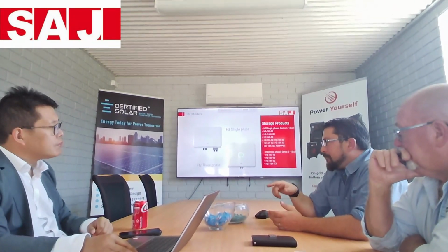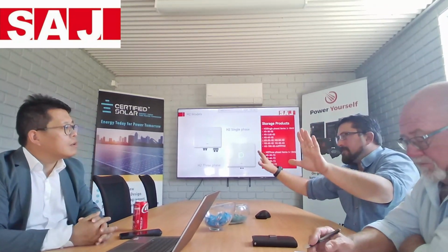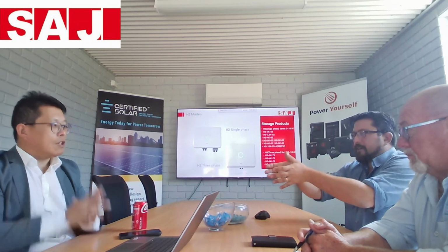Here's a good technical question for you: if we've got say 3, 10 kilowatt 3-phase inverters, and 3 battery stacks, will that system be able to put out a continuous EPS load of 10 kilowatts? Yes, in that parallel form. So if the customer's drawing 25 kilowatts of live power, all those inverters and the battery system will act as one to power that. Correct, we can parallel these inverters and they can talk to each other.